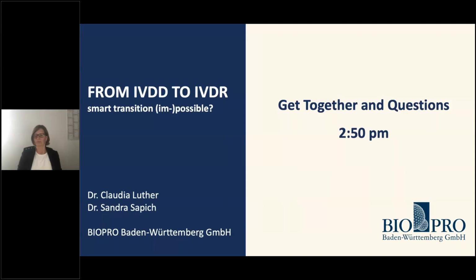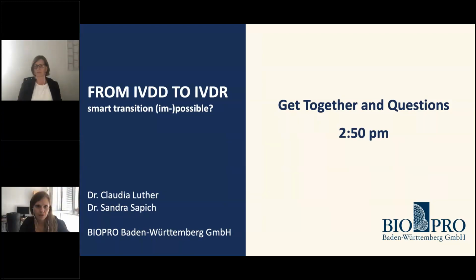And with IVDR, this will be even worse than with MDR, because IVDs often have very specific storage temperatures, storage conditions that hardware MDR devices won't have. And you will have to ensure that your distribution chain is able to guarantee the +5 to +15 degrees throughout this distribution chain. And if you do not qualify them correctly, you will have a problem, because notified bodies will have to dig into that. Yeah, we'll have to ensure.